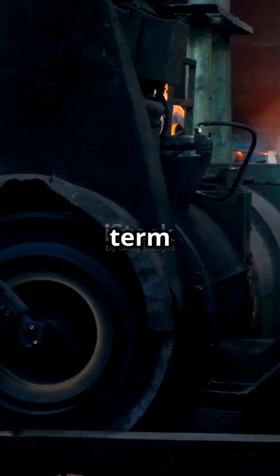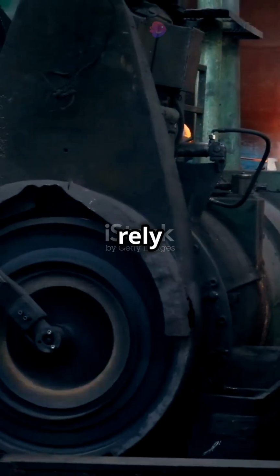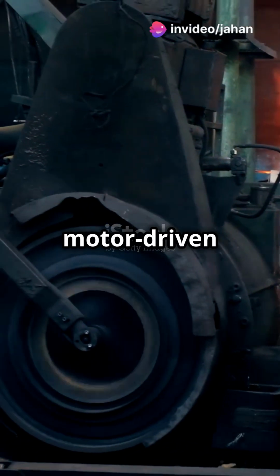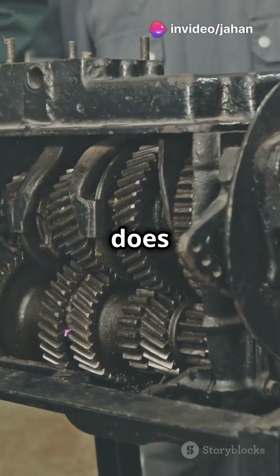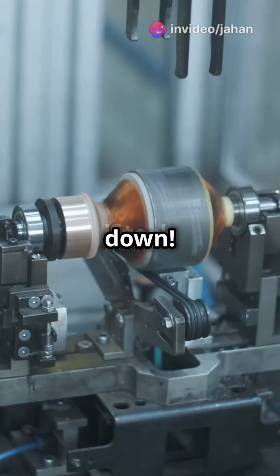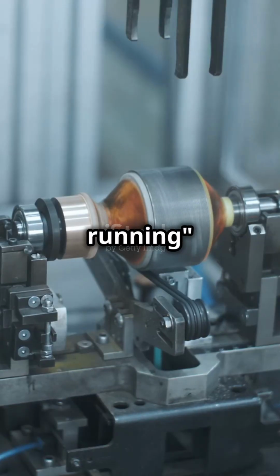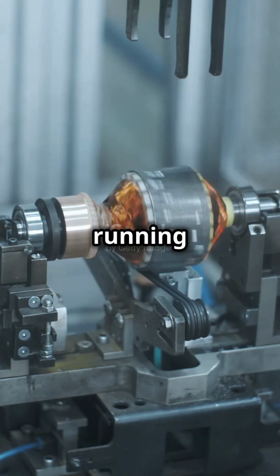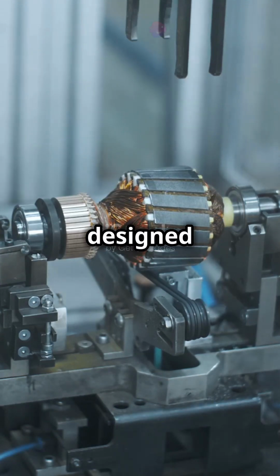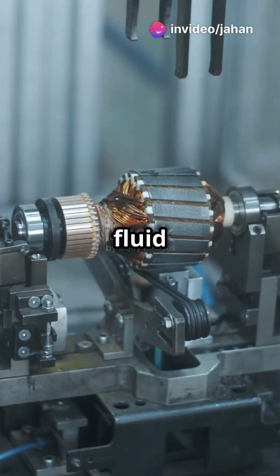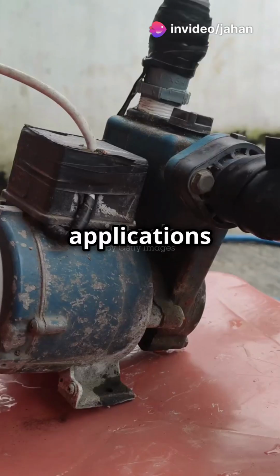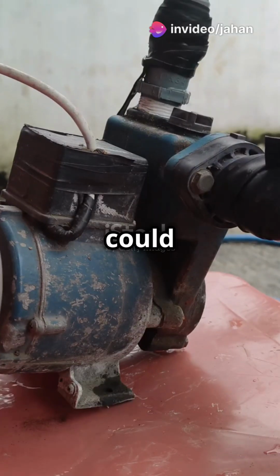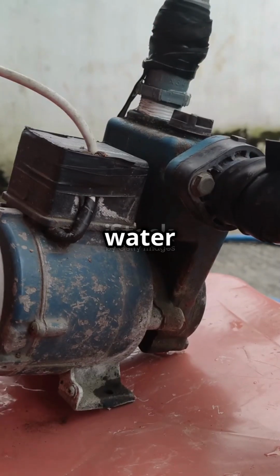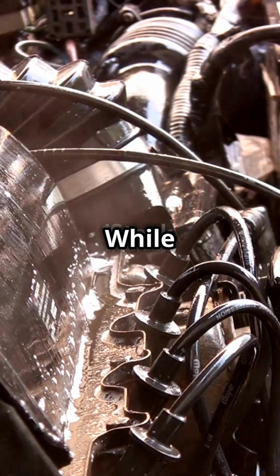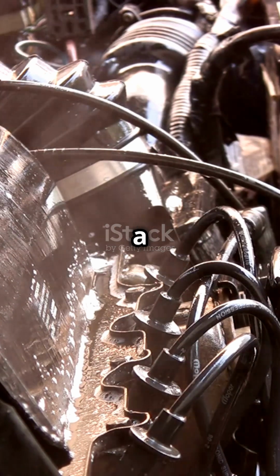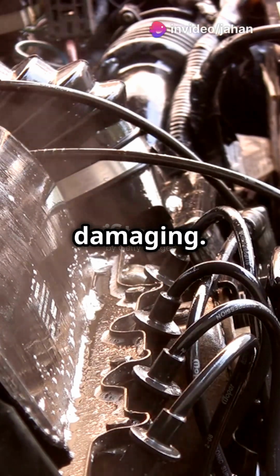You might have heard of this term before, especially in industries that rely on pumps, compressors, or other motor-driven equipment. But what exactly does it mean? Let's break it down. In simple terms, dry running refers to a situation where a motor is running without doing the work it was designed for, typically because there's no fluid or load to drive. In applications like water pumps, for instance, this could mean the motor is running without any water flowing through the system. While it may sound harmless, running a motor in a dry condition can be extremely damaging.